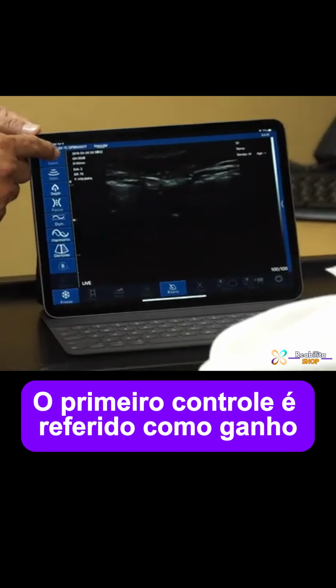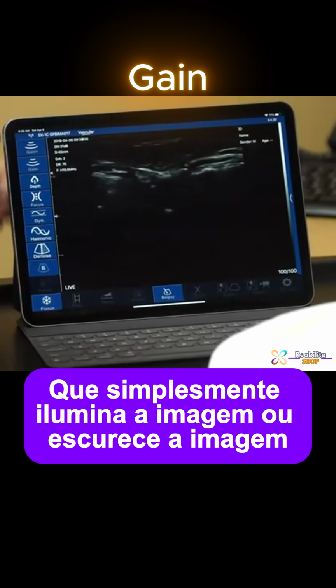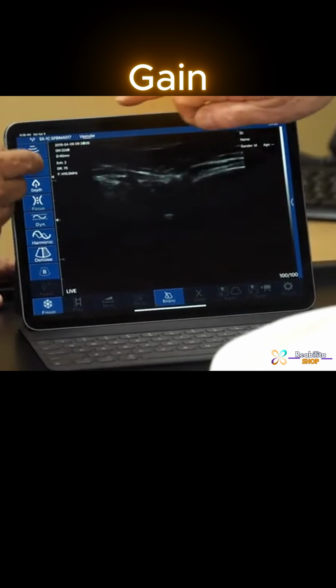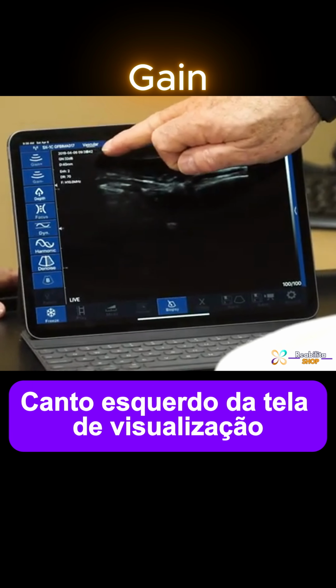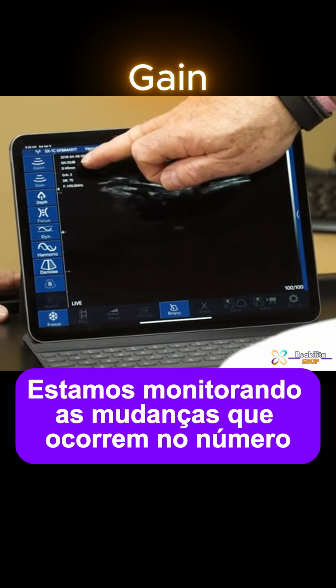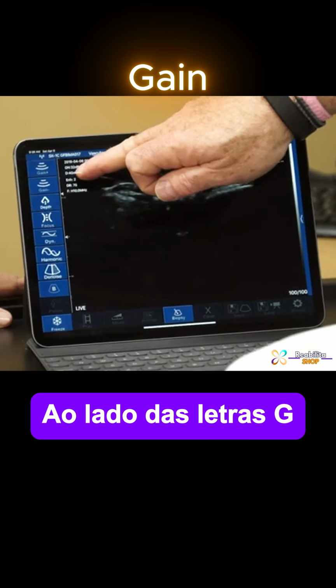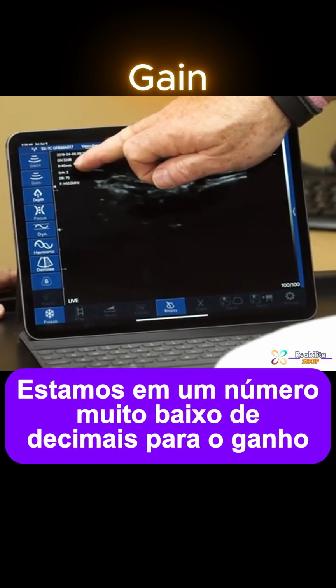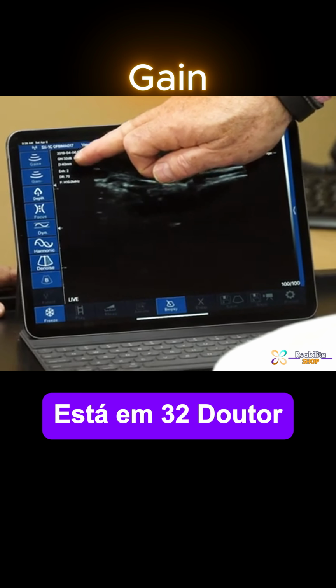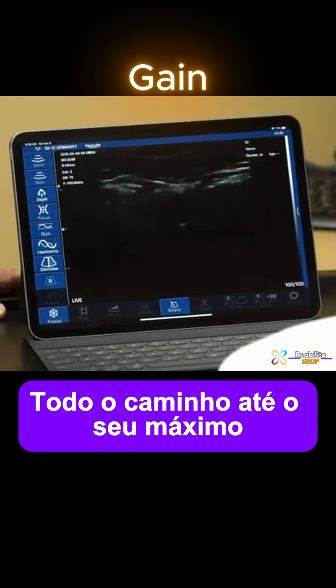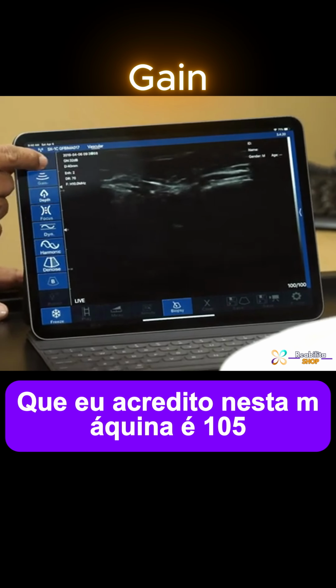The first control is referred to as gain. That simply brightens the image or darkens the image. The parameters are displayed in the upper left-hand corner of the viewing screen, and here we're monitoring the changes that occur to the number next to the letters GN for gain. Right now we're at a very low number of decibels for the gain. It's at 32. Dr. Garcia will be increasing the gain all the way up to its maximum, which I believe on this machine is 105.